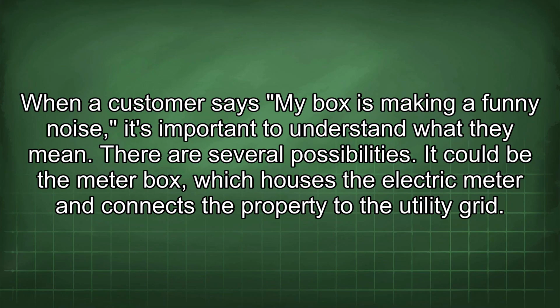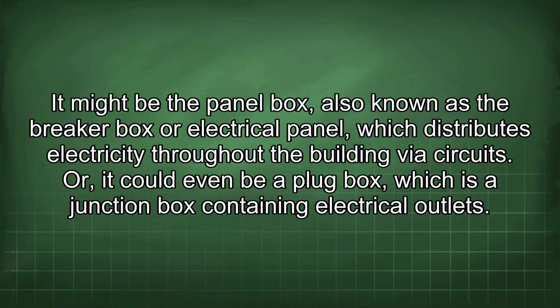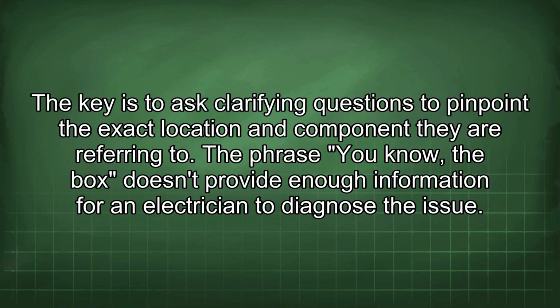When a customer says my box is making a funny noise, it's important to understand what they mean. There are several possibilities. It could be the meter box, which houses the electric meter and connects the property to the utility grid. It might be the panel box, also known as the breaker box or electrical panel, which distributes electricity throughout the building via circuits. Or it could even be a plug box, which is the junction box containing electrical outlets. The key is to ask clarifying questions to pinpoint the exact location and component they are referring to. The phrase "the box" doesn't provide enough information for an electrician to diagnose the issue.